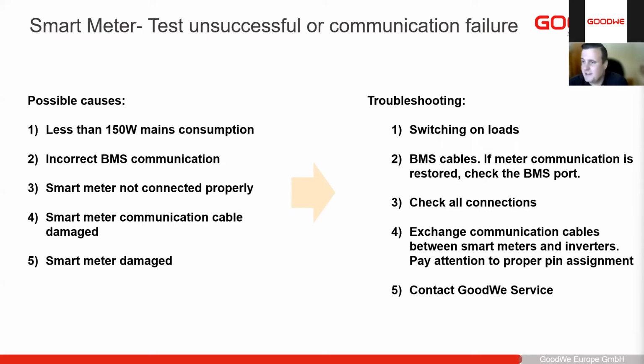I'll often get customers say, run it once, it gives me one answer, run it again, it gives me another answer. So we always need to make sure that each phase is drawing at least 150 watts from the utility. So if the PV is on, if we have batteries, we're covering all the loads, go and turn more loads on. Put as much load as you can on in the home so that the inverter can calculate accurately.